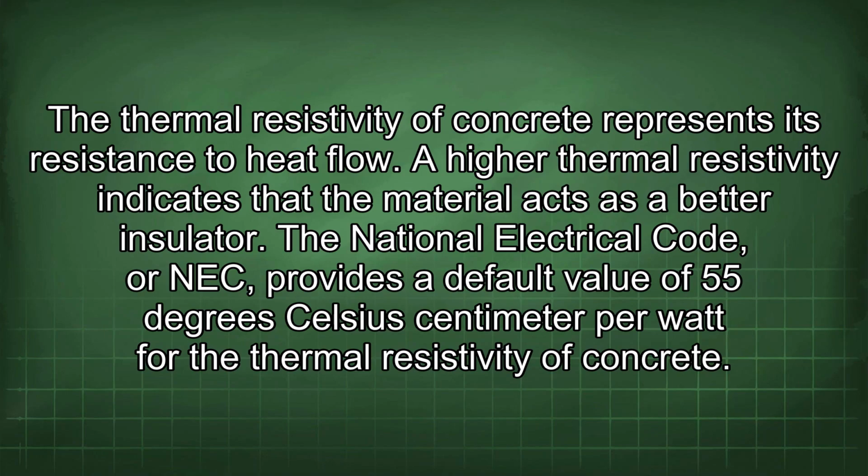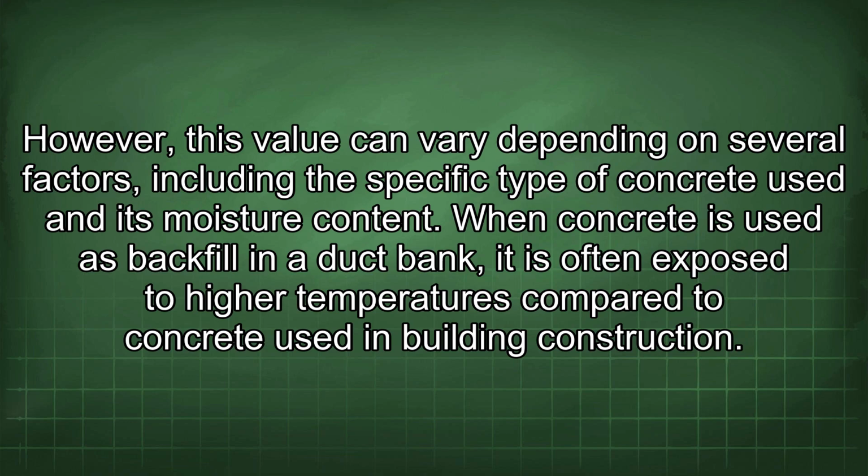The thermal resistivity of concrete represents its resistance to heat flow. A higher thermal resistivity indicates that the material acts as a better insulator. The National Electrical Code, or NEC, provides a default value of 55 degrees Celsius centimeter per watt for the thermal resistivity of concrete.